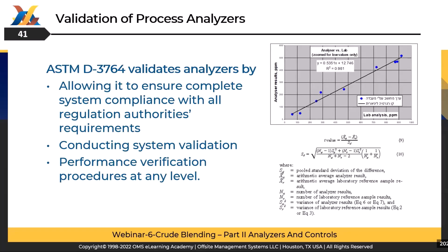After analyzer system installation, the following on-site and off-site services should be provided by system integrators. Equipment assembly and supervision, pre-commissioning and commissioning procedures, connection, wiring and system integration, startup, setup, software configuration, calibration, validation according to the ASTM standard, and the site acceptance test of the complete analyzer systems. Training of customers, operators, and maintenance personnel, theoretical and practical training. Fulfillment of any warranty obligations and performing any required repairs. Long-term maintenance and remote technical support and consulting.